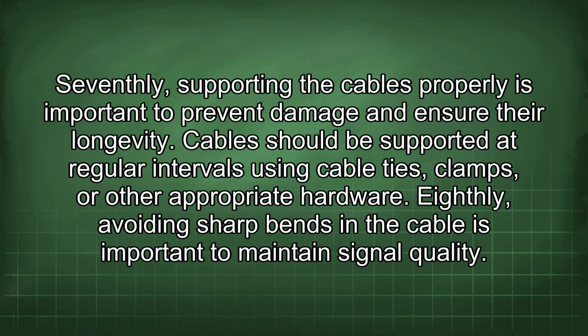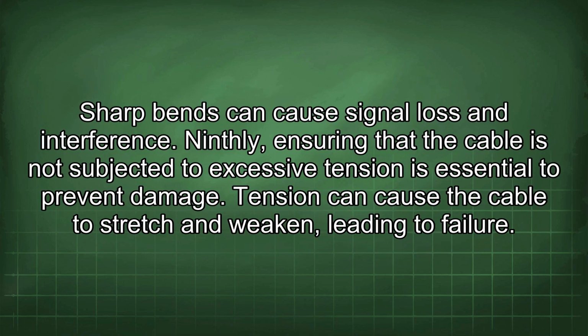Seventhly, supporting the cables properly is important to prevent damage and ensure their longevity. Cables should be supported at regular intervals using cable ties, clamps, or other appropriate hardware. Eighthly, avoiding sharp bends in the cable is important to maintain signal quality. Sharp bends can cause signal loss and interference. Ninthly, ensuring that the cable is not subjected to excessive tension is essential to prevent damage. Tension can cause the cable to stretch and weaken, leading to failure.